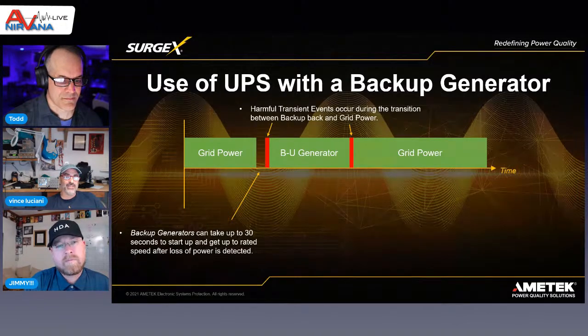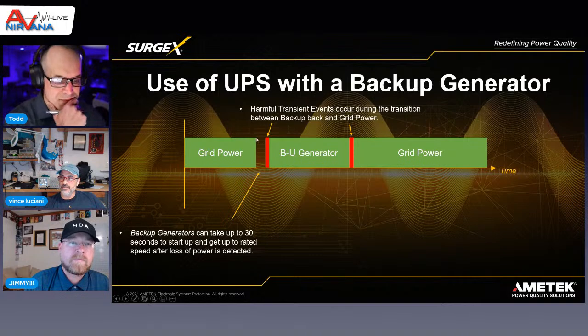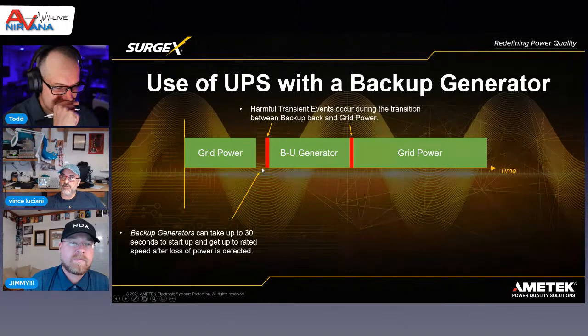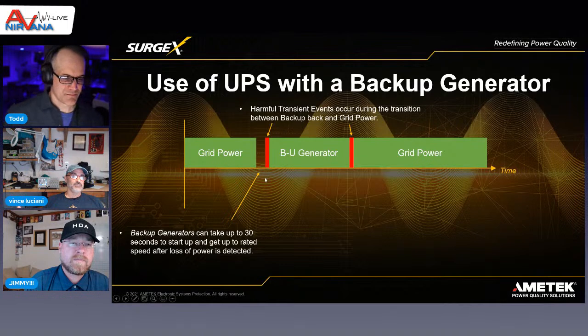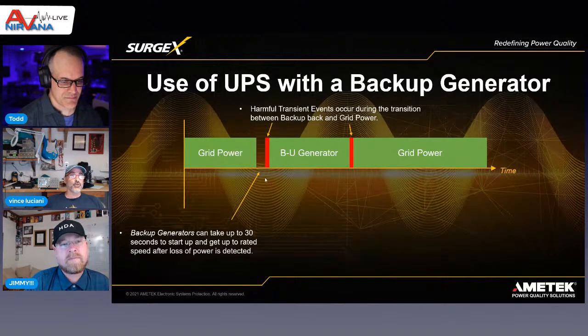So I put this kind of timeline together. Going from left to right, you're sitting here on grid power, everything's good. Then the power goes out. Well, the generator, if you don't have a UPS on there, is going to take 15 to 30 seconds to detect and come up to speed. And then when it finally comes up to speed, you're going to get this incredible transient because everything in your house has been starved of power. When that generator comes on, it puts an incredible transient that's similar to a surge—it is actually a surge. And then you're on backup generator until the power comes back on, and then you have a switchover, another transient event, and now you're back on grid power.